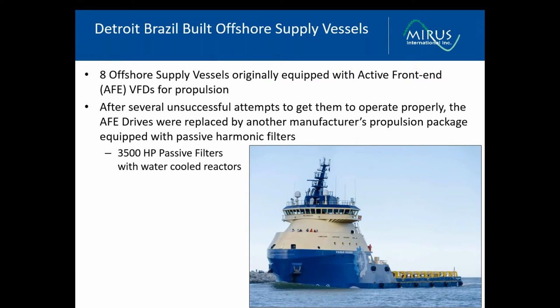This project involved a total of 8 IMR vessels, or inspection, maintenance, and repair vessels used in the oil and gas industry. These vessels were built in Brazil. They originally were designed around active front end or AFE drives for the propulsion systems, but the manufacturer was never able to get them to work due to the high frequency noise they introduced. Eventually, they were stripped out and replaced by another manufacturer's propulsion system utilizing 6-pulse VFD and the MIRUS passive filter.